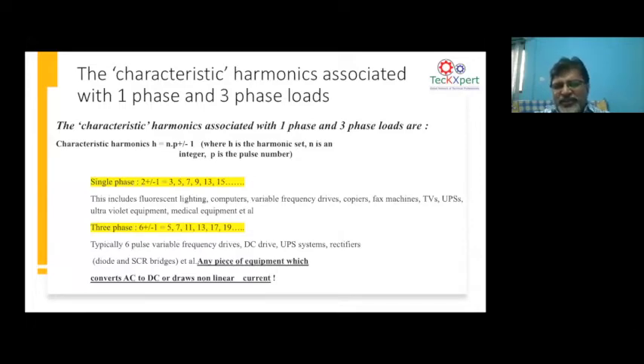And the diodes do the function of converting the AC to DC. Now in a single phase, you use 4 diodes. If you look at any SMPS supply, you can see 4 diodes in the circuit. And in a 3 phase, you use 6 diodes. In a variable frequency drive, when you have 6 diodes, we call it a 6 pulse drive. But in simple electronic lighting or computers, you don't call it like that. You rather call them SMPS based supplies.